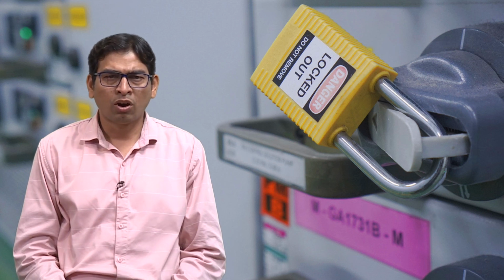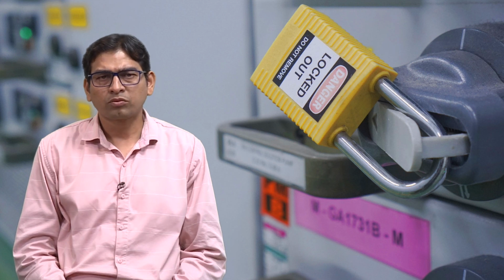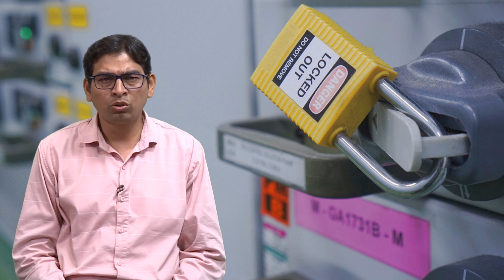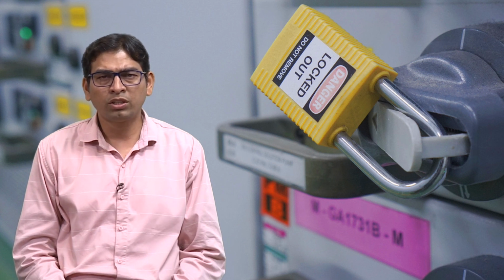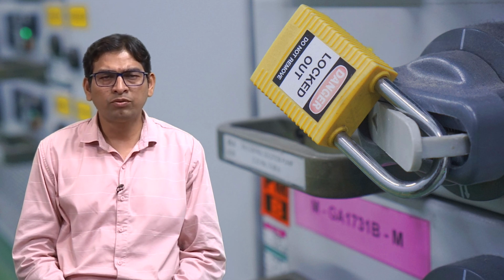Once the lockout tagout procedure has been accomplished on the electrical system, you should try to start and operate the equipment to make sure that the lockout has been done correctly. You should not see any movement. You also need to test the circuit with a voltmeter or similar device.